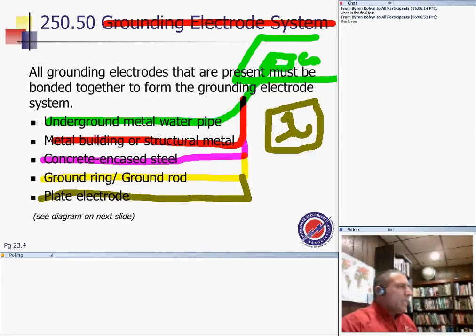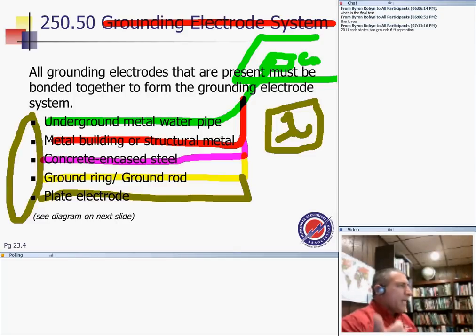So the steel of the building, if it's a steel building, not residential. Well, it's a little bit confusing. Say the steel of the building, you only need one. But if all the others exist in the building, you have to bond them all together. Make sense, guys? You only need one, but if the others exist, then you need to bond them to the system. For example, if I have a commercial building and the structural metal of the building is tied to the ground, and that's a good grounding electrode system, that's all I need. But if I have a water system coming to my building, I need to bond to it. Or if I have concrete foundations, I need to tie to them. If I have a plate, you do the plate. So if I have a water pipe, I need to tie to it.